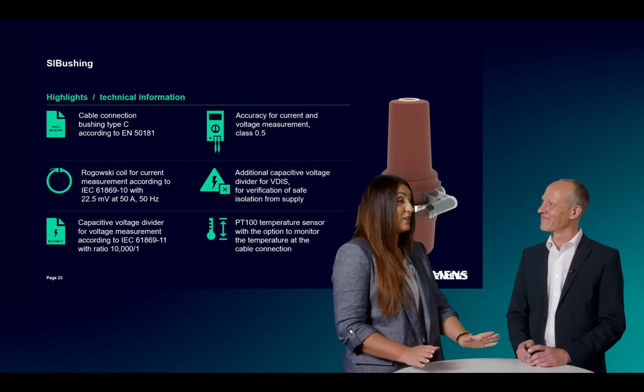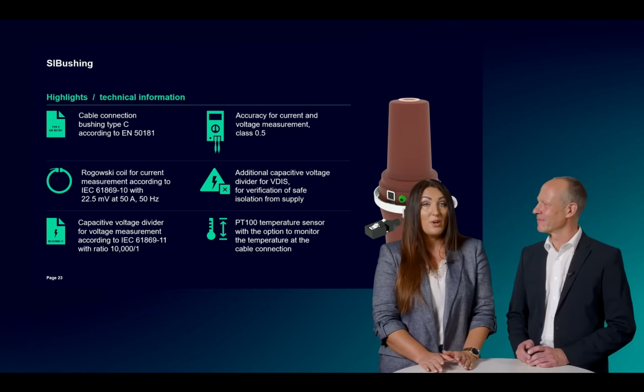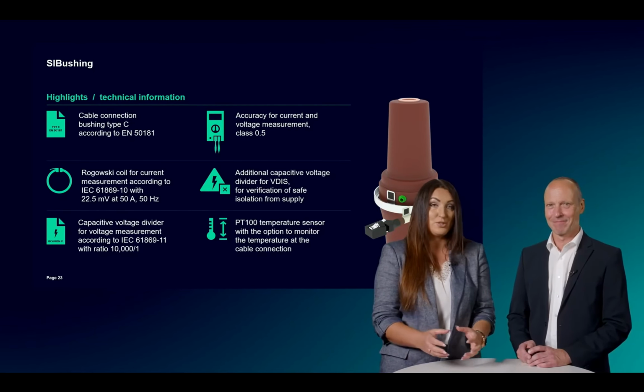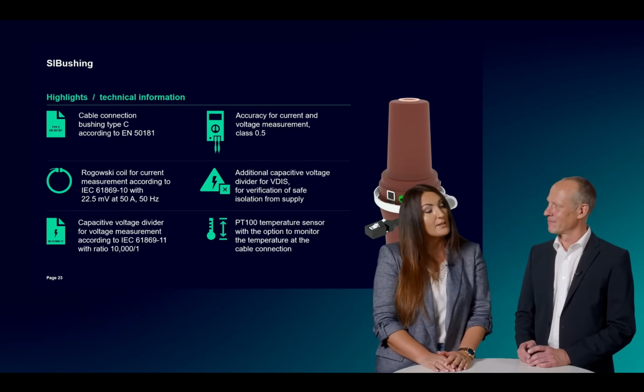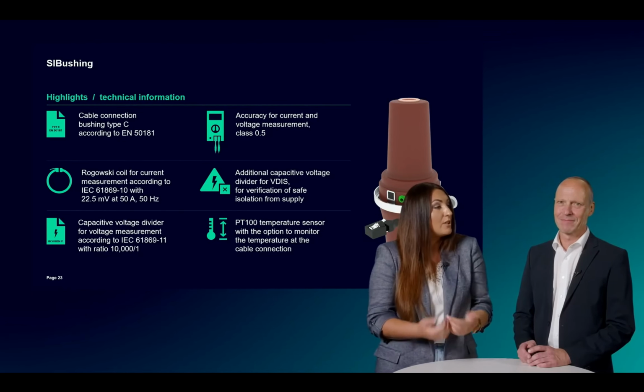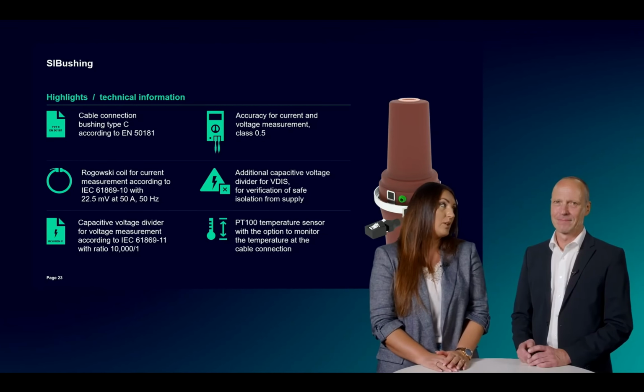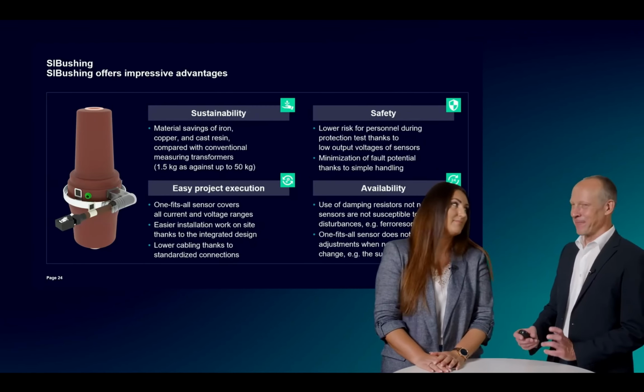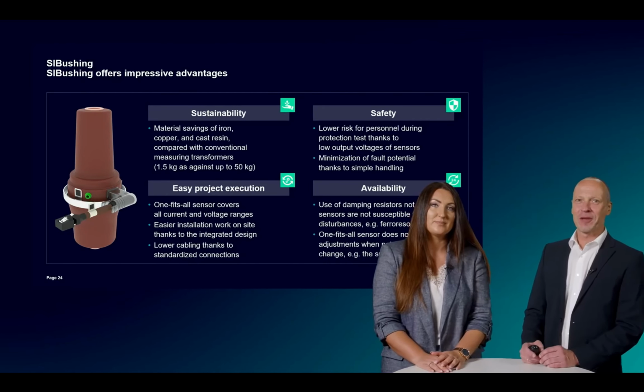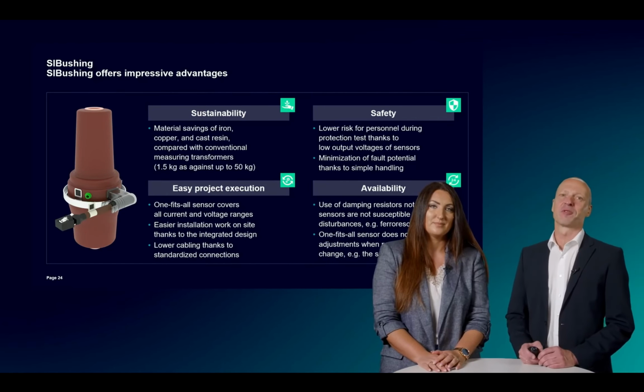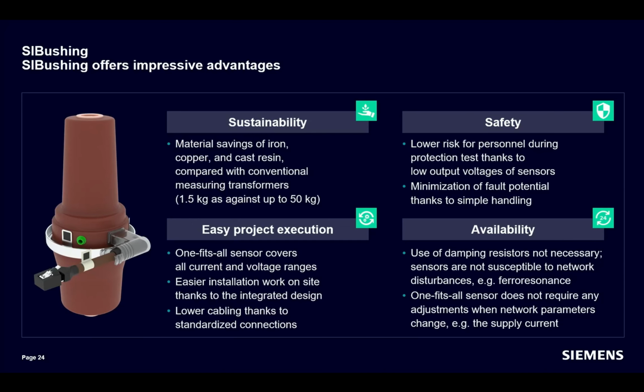Wow, so this is a major innovation that Siemens has done, with four integrated sensors in such a small component. But will our customers have further advantages from the SI Bushing? Yes, Leila. We are contributing also to the topic of sustainability with our innovative SI Bushing. It provides massive material savings of iron, copper and cast resin, as its weight is only around 1.5 kilo per piece, compared with conventional CTs and VTs with a weight of up to 50 kilogram per piece.